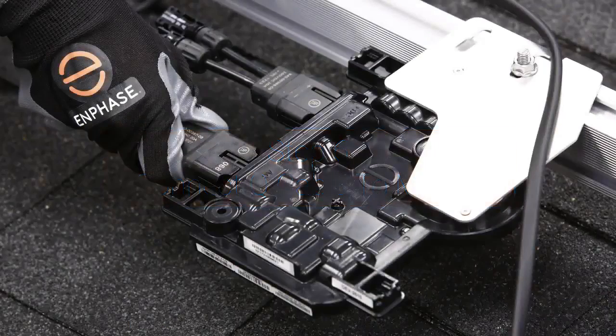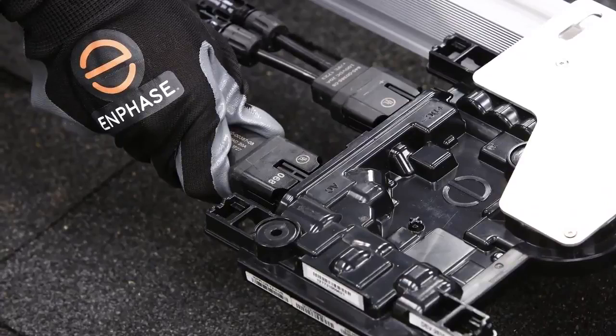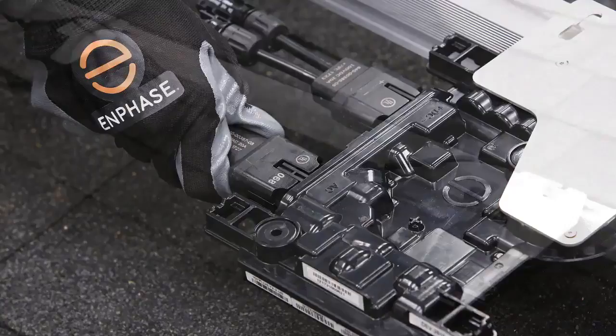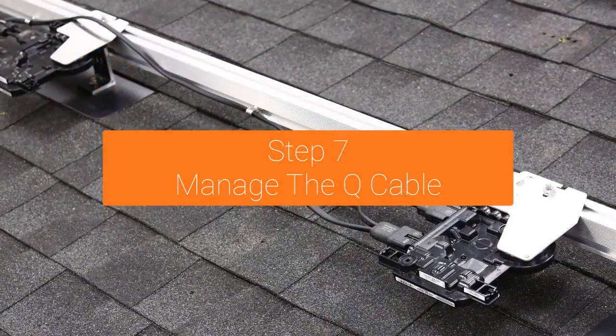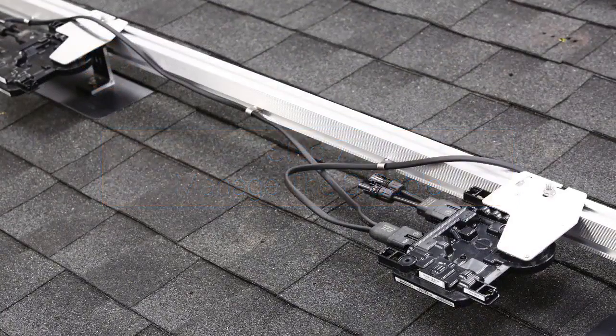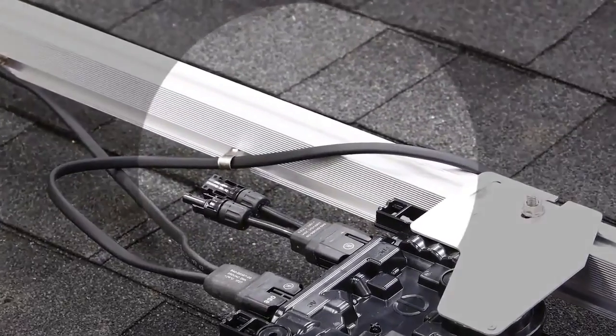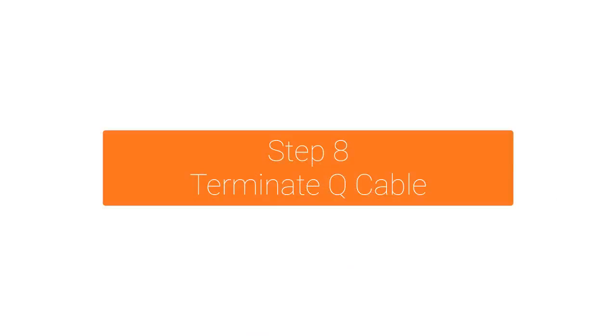Connect the AC connector of the Q cable to the microinverter. Listen for the click as the connectors engage. Ensure that you have ample bend radius and do not kink the cable. Attach the Q cable to the rack using the recommended clips. Use a clip to hold the Q cable before jumping between rails. Terminate every open end of the Q cable with a Q terminator.